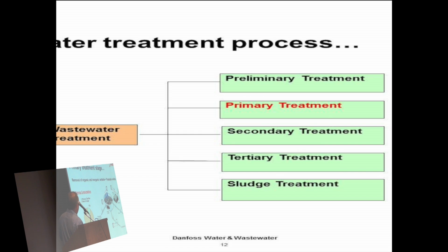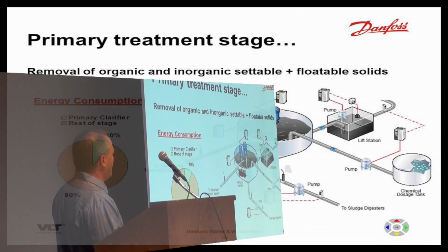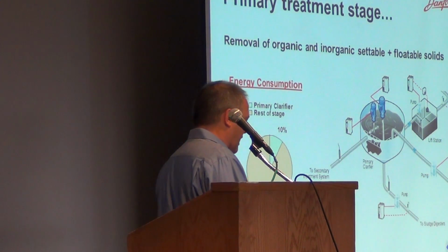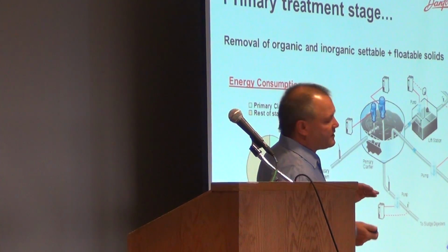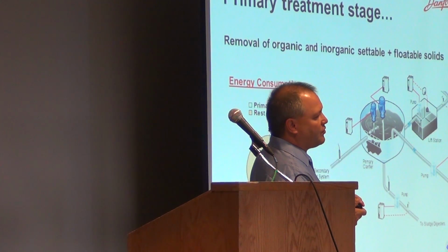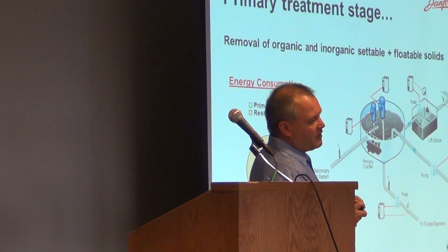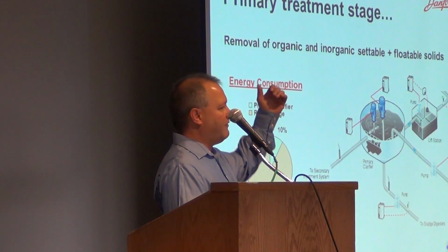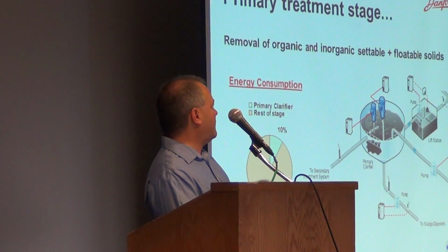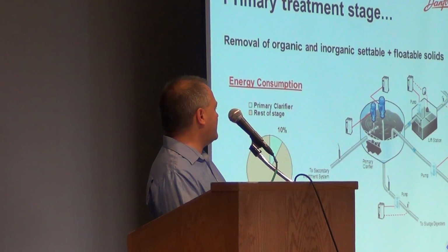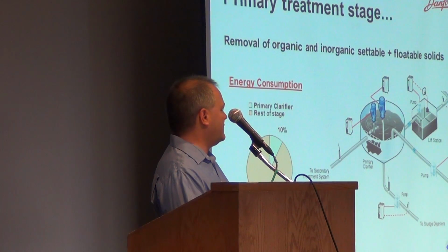Energy consumption in the rest stage, we're really talking this 10%. That's where we're going to help with the clarifier. Anytime you can get the whole system on drive, it smooths the system out, it gives you a better control. With the drive on the system, you have infinite control with a valve. You might have quarter-inch clicks on your valve where you need to be halfway between, but you can't because there's no way of locking that valve in that position.